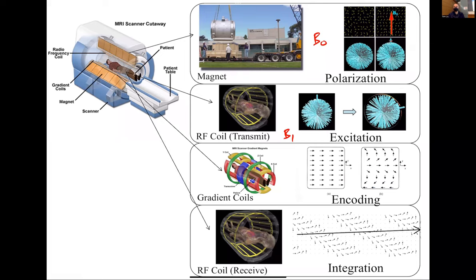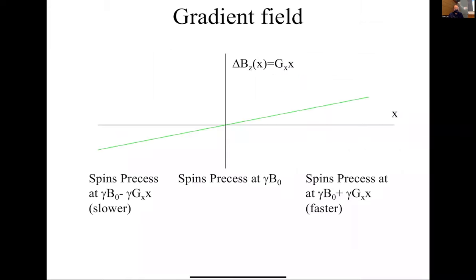I'll spend quite a bit of time on encoding because that is essentially how we make our images. So we're going to use these gradient fields, and this is going to create a delta B-Z field. Remember, this is the isocenter — spins at the isocenter precess at gamma times B0. When we turn on this gradient field, the field here is stronger, so spins here precess proportional to the local magnetic field. The Larmor frequency of spins in the stronger region is higher, and in the weaker region it is lower.